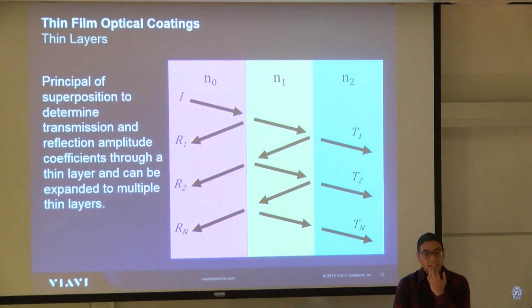Yeah, so a couple of things to address your second question actually, about how different samples have different textures. A lot of that came into the optical design of this. How do we make sure that there's uniform light that's illuminating all of the pixels under it? If you have something that's highly specular, where you shine it and it's like a mirror, then you might have hot spots. So we use special optics in order to remove those hot spots and uniformly spread light throughout.